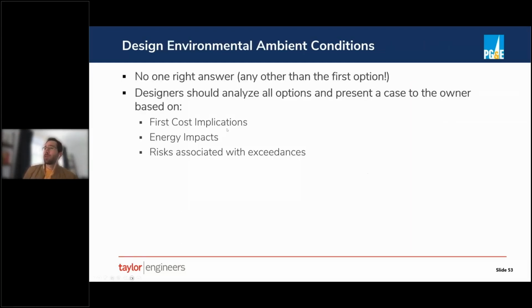So again, going back to the statement I made earlier, there's no one right answer for that facility other than obviously the one that they picked. And when you're coming up with recommended design environmental conditions for a given facility, there are 3 factors you need to weigh. One is first cost implications. Second is energy impact. And the third is the risk associated with exceedances of those design conditions. So the more conservative or the higher you make your design conditions, the higher the first cost is going to be, because it will drive the size of your mechanical equipment up, as well as the electrical infrastructure that's supporting that equipment. There can be energy costs, ongoing energy impact as well.